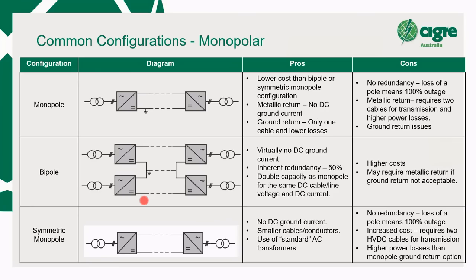The downfall, the con, is the higher cost, you've got twice the converters. Yes, they're half the rating, but there's just generally more infrastructure. And you may require a metallic return. So, you know, you may need three cables. For short cables, it's probably not an issue. If you've got longer cables, that may become a problem.